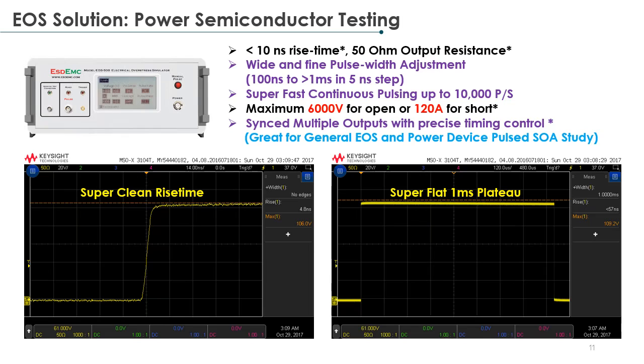Our EOS solution is an extension on our TLP solution. It can go from a minimum of 100 nanoseconds all the way up to 1 millisecond in 5 nanosecond steps. Unlike the TLP, it supports much faster continuous pulsing, up to 10,000 pulses per second. Also can offer synced multiple outputs, unlike the TLP. And it is much more customizable than the TLP. Typically, our standard unit is a 50 ohm output impedance, but we are open to customization for lower or higher values. Rise times for this can get low, pretty fast, depending on pulse level. It can get as low as under 10 nanoseconds. The maximum current exceeds that of the TLP, up to 120 amps. So this, alongside the longer pulse widths, makes for good power semiconductor testing, SOA studies, Wunsch bell curve generations, and many other applications.